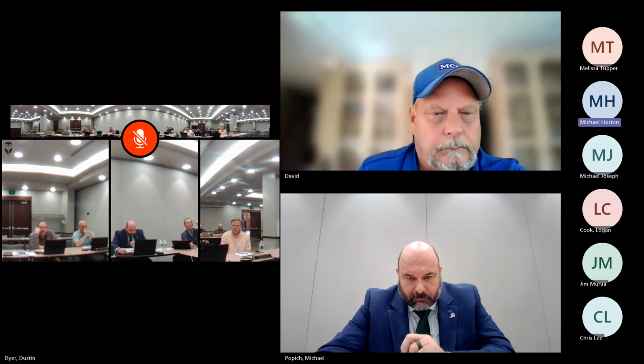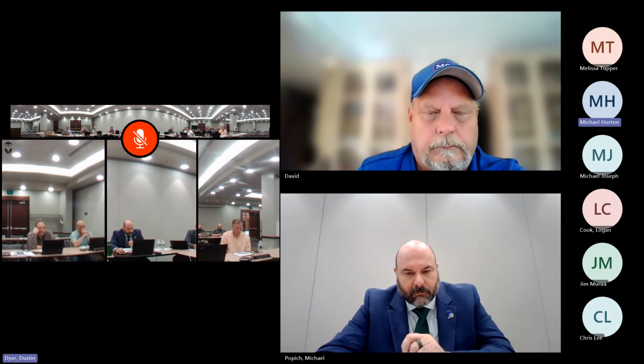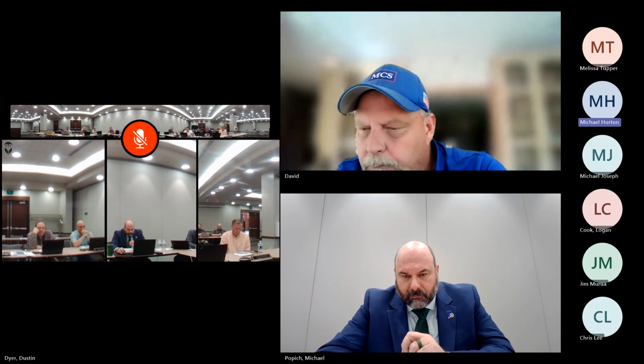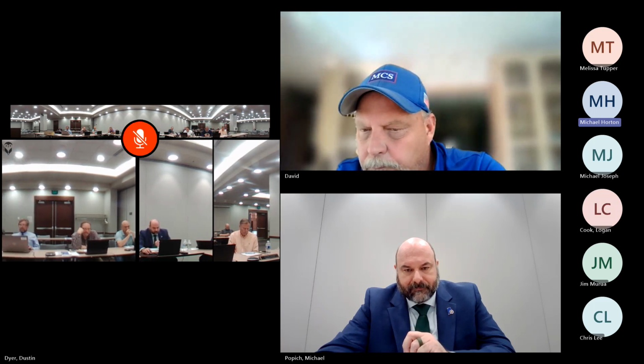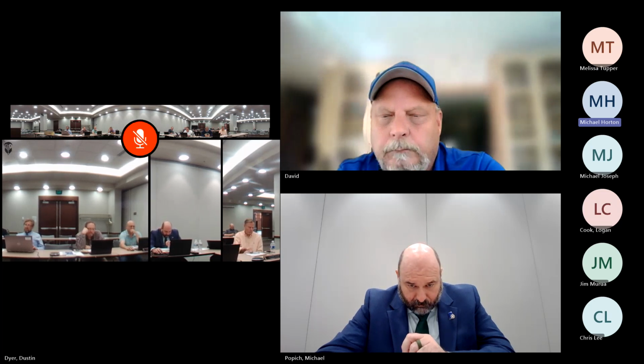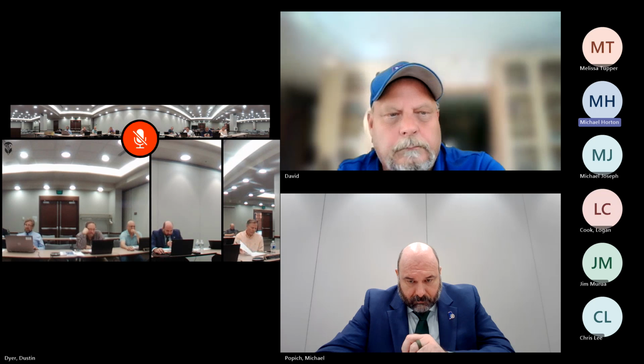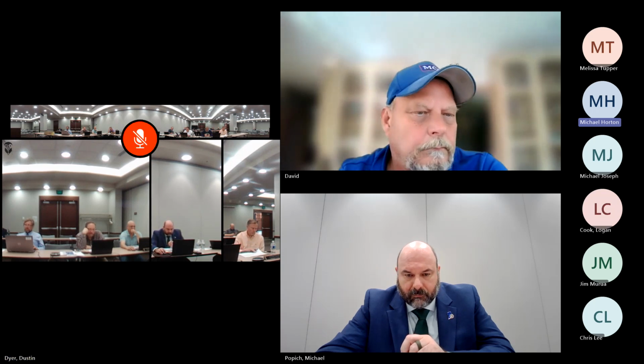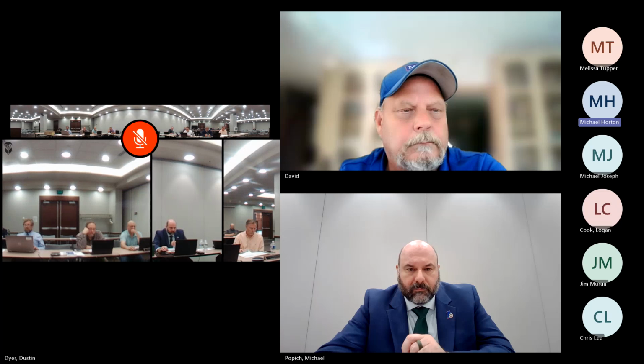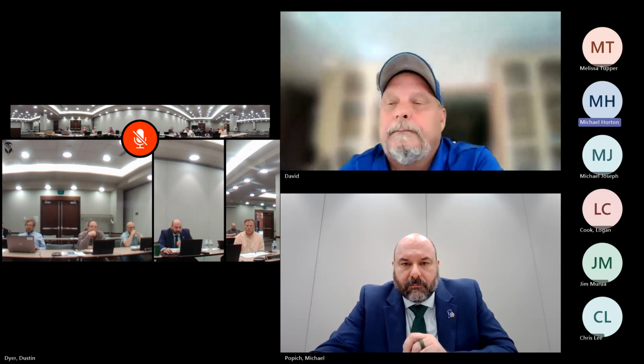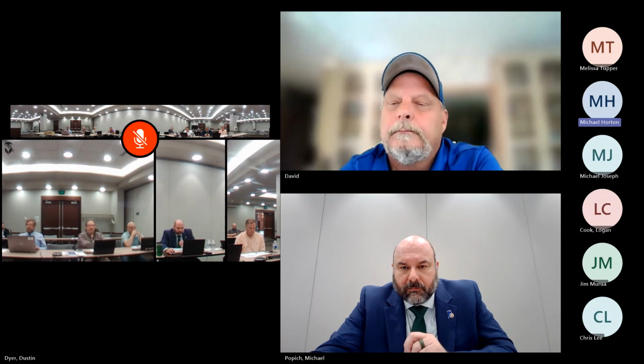We do think it may satisfy the intent of the code, particularly because the first floor has such a low percentage of openings. In the area between 3 and 5 feet, even counting the entire facade as a whole, we still do not comply, which is why we're noting the sprinklers in the balconies themselves. If we consider the openings in the sprinklered balconies, we would comply and meet the requirements of Table 705.8 on floors 1 through 5.